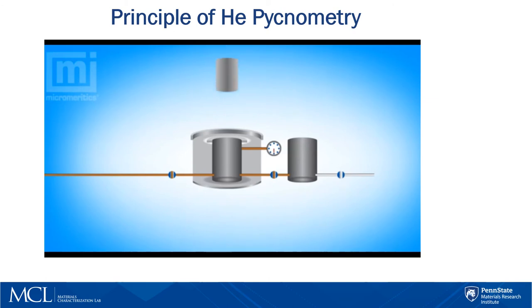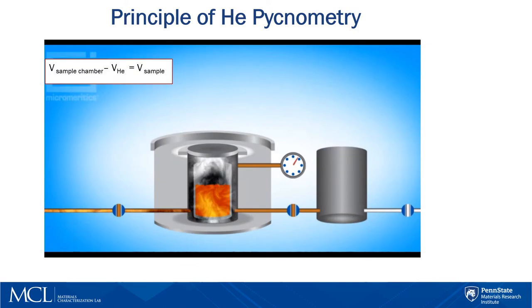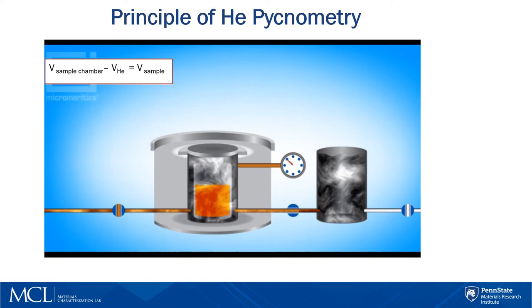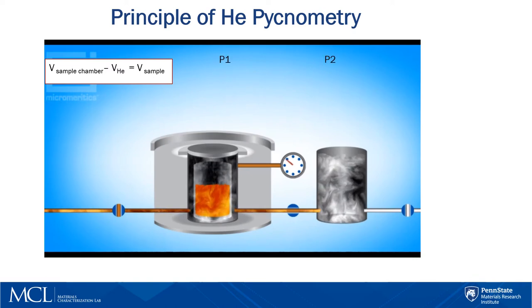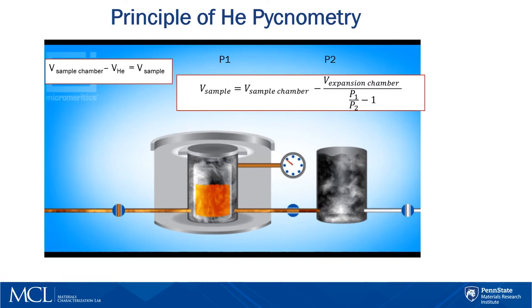The sample is loaded into a sample chamber of known volume. Then the analysis gas is introduced and released into a second chamber, with molecules rapidly filling the chamber including tiny pores of the sample. The difference between the volume of helium in an empty chamber and the newly introduced helium volume is equal to the sample solid phase volume. We measure pressure in the sample chamber, then the gas is released into the second chamber and we measure that pressure as well. This allows us to calculate sample volume, and then knowing the sample mass, we can calculate the density.